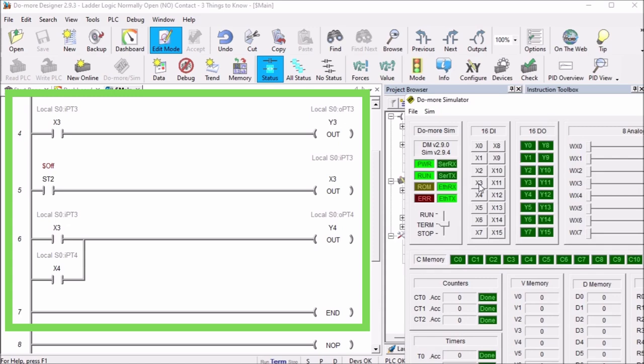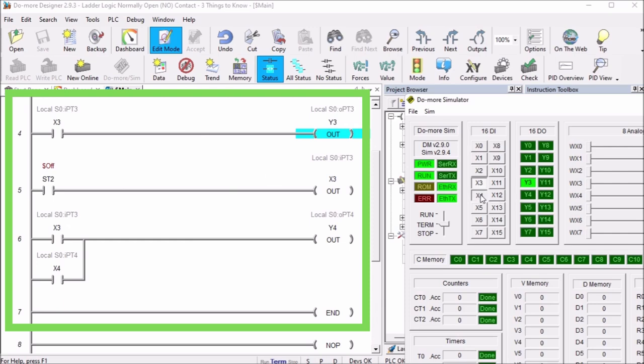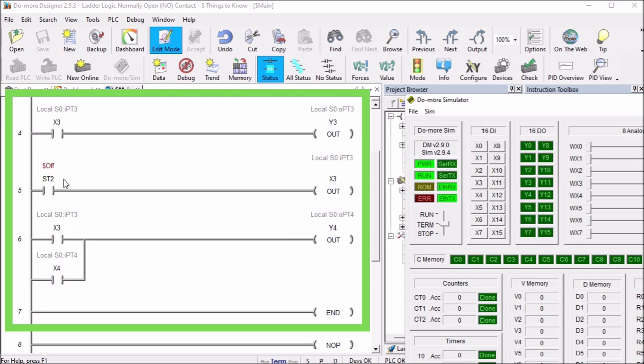In this case here I will turn on X3. X3 turns on Y3, however Y3 down here is not turned on and output Y4 is not turned on because here we have the normally off condition and we're turning off X3. So we're acting as an input to turn off that internal memory bit so it will not activate. Think of all the inputs that we have as just memory internally that we can see, so we can turn that on and off or manipulate the bits as we please within that controller. You can see if I do X4 it'll turn on Y4, but X3 will not turn on Y4 because of this rung here causing that internal memory bit to turn off.